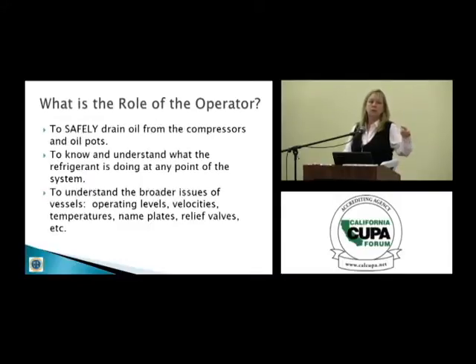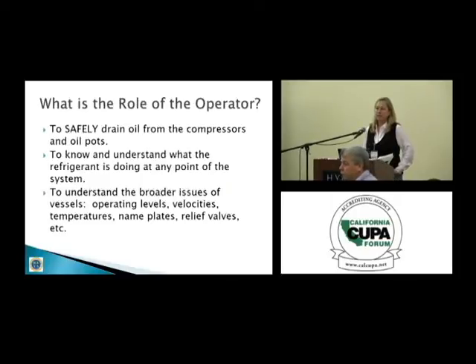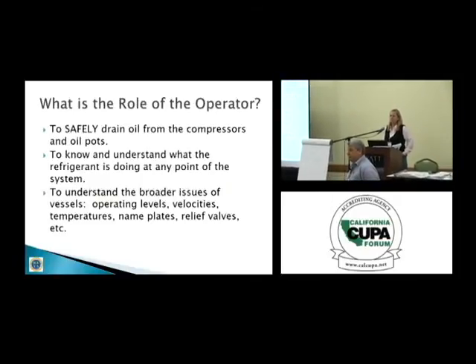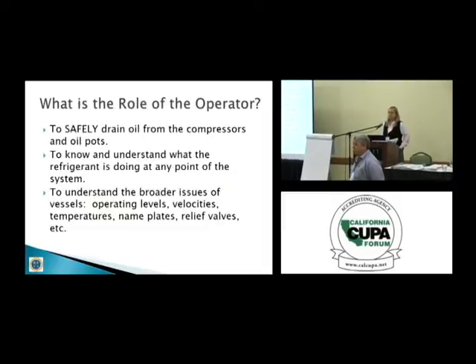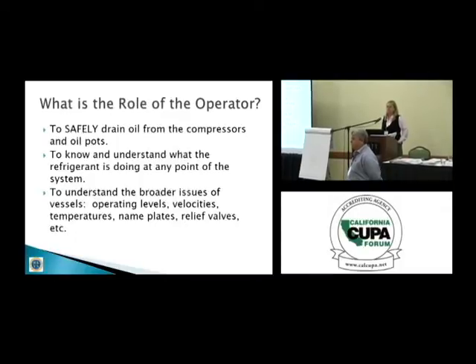So the question is, I have an old piece of equipment, the nameplate pretty much can't be read, but you have the U-1A form. What do we do? Yeah, you can apply to the National Board to get a duplicate nameplate, and they need that U-1A information, et cetera, and they'll contact the manufacturer and authorize a new data plate to be made. That data plate needs to be installed by a certified individual.